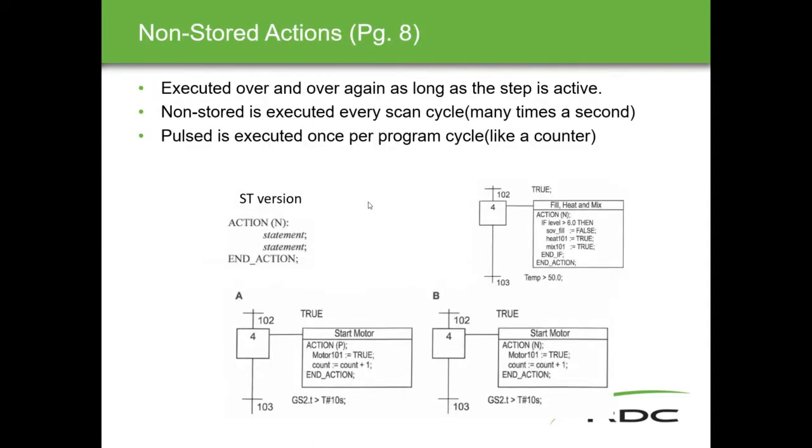Okay, we'll talk a little here about stored and non-stored actions. A non-stored action is executed over and over again as long as the step is active. And again, that's identified here, non-stored actions, by having this N in here, as you'll see. N over here for a non-stored action, P over here for a pulsed action. Again, identification is half the battle. Non-stored is executed every scan cycle, so many times a second, whereas pulse is only scanned once per program cycle, like the counter.